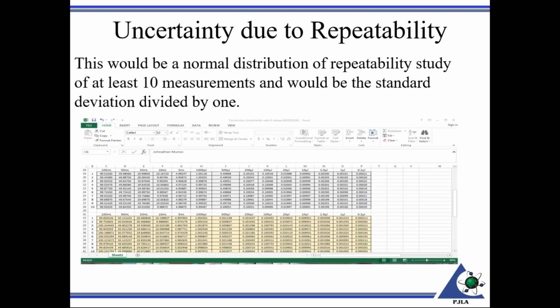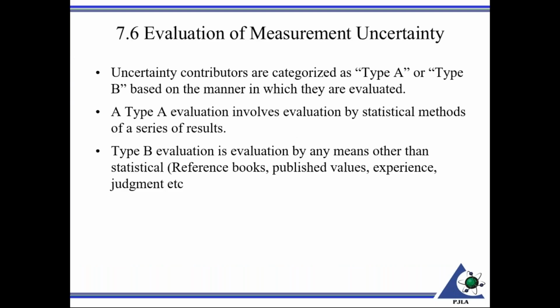Repeatability, that was the third one we mentioned. So this would be a normal distribution of at least 10 measurements and would be the standard deviation divided by 1. Uncertainty contributors are categorized as type A and type B. Type A evaluation involves evaluation by statistical analysis of a series of results, i.e. the repeatability studies that we just looked at. Type B evaluation is evaluation by any means other than statistical. You come off the calibration reports, reference books, published values, experience, judgments, etc.